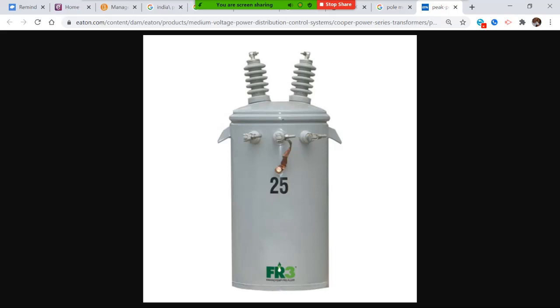We'll say for this transformer's sake, I don't see the nameplate, that we have 7,200 volts coming in, and this is for a residence. So how much voltage do we get out of this? 120, 120 and 240 -- 120 each one individually, and the combination of the two, 240.